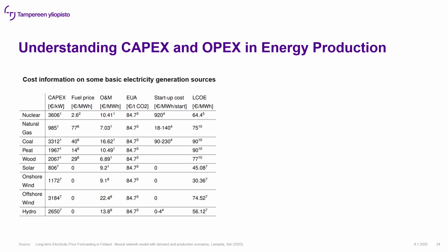Startup costs. So if you start a fluidized bed boiler up, it costs a lot more than firing a gas-fired turbine. So the startup costs of that district heating station next to the fire station here, 100 megawatt oil burn, are a lot less than the startup costs for this boiler in the other corner, the biomass plant.